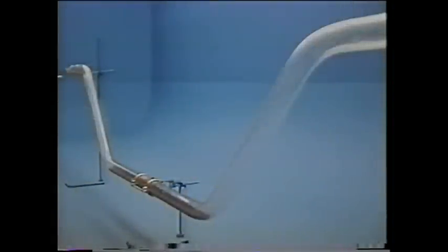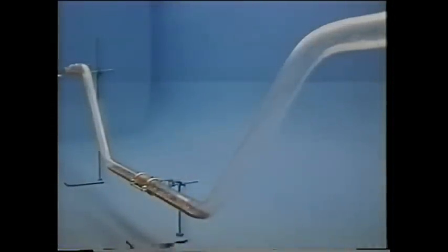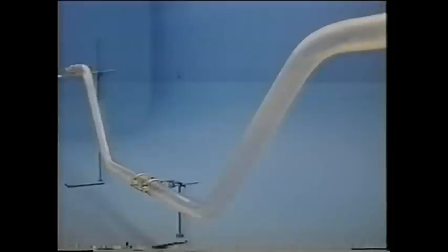In many places, the gas pipelines dive under rivers and canals. At low gas velocity, liquid can accumulate in these crossings. In autumn, when the gas offtake rises, the gas velocities increase, creating conditions likely to give rise to liquid being blown out of these crossings in slugs. At gas velocities in excess of about 4 meters per second, the condensate flows through the crossing without any difficulty.